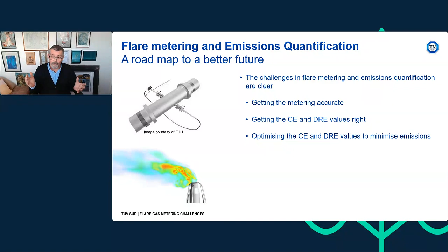And then also providing operators and regulators with calculations which can be understood, audited, and verified. We're quite happy to use ISO calculations and AGA calculations and GERG calculations for gas export, and they're all public domain. They can all be independently verified. So why don't we use them for flare gas meters? Nothing against the proprietary calculations, but if I want to verify my emissions reporting, why don't I verify it using auditable and publicly available calculations?